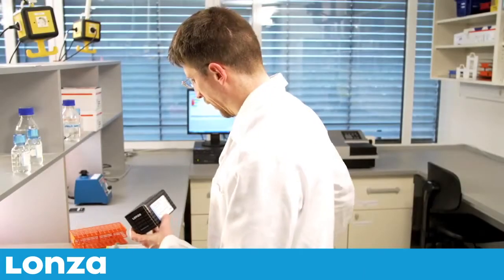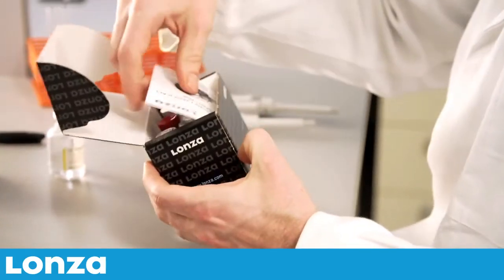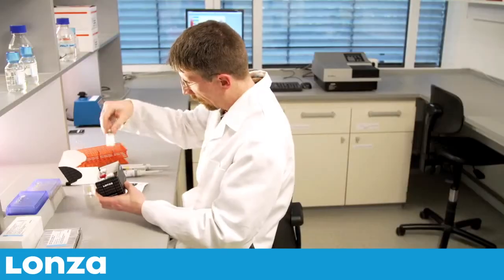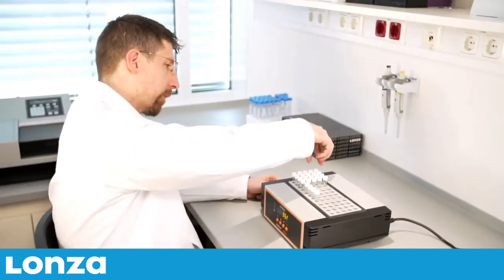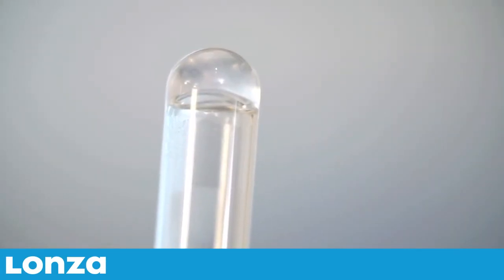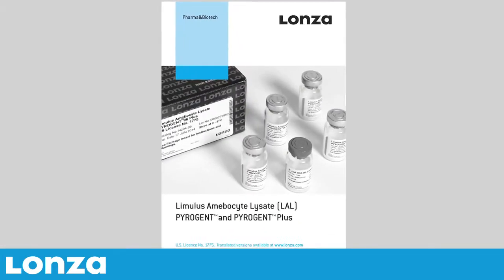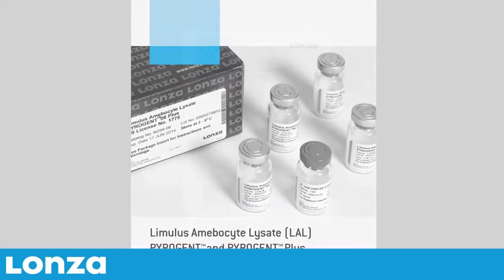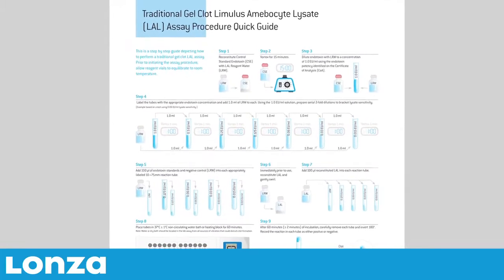The Gel Clot assay is run in depyrogenated glass tubes that are placed in a water bath or dry heat block at 37 degrees Celsius. After a one-hour incubation period, the tubes are inverted 180 degrees. A firm clot that stays in the bottom of the tube indicates a positive reaction. The Pyrogent Assay Package Insert and Quick Guide provide complete, easy-to-follow instructions for performing the assay.